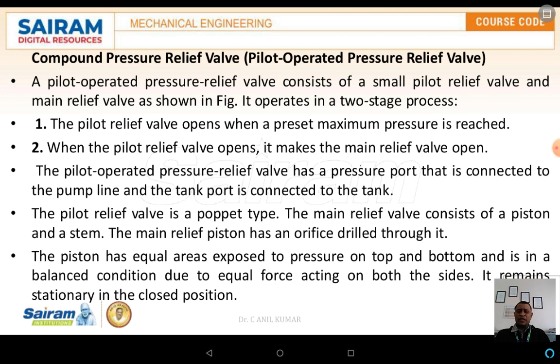In the compound pressure relief valve, the pilot relief valve operates first up to maximum pressures. Once it reaches the maximum, the pilot relief valve opens. The pressurized oil then passes through the main relief valve and is let out to the tank. This is the operation taking place in the compound pressure relief valve.